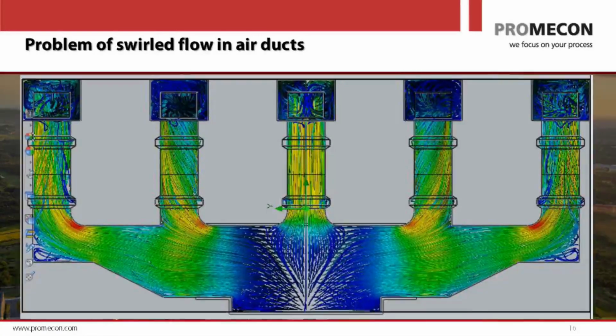It only measures the value, delta P or delta T. It doesn't measure any direction. And if you have a strong spin in your flow, the measurement is simply wrong because the spin adds to the air velocity, but it does not add to the air mass flow through the duct. That's the very big difference. The air velocity gets larger by the spin, but the air mass flow through the duct does not.